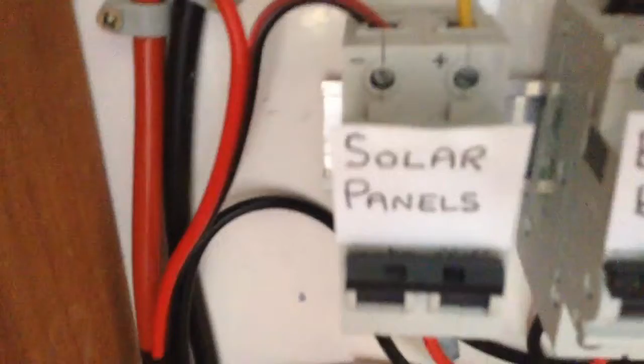From the ammeter we go to a DC circuit breaker. It is an overload protector and a cut-off switch in one. This is a double pole circuit breaker. It's recommended to use double pole isolating breakers - it's a breaker and an isolating switch together, so it disconnects both the positive and the negative of the solar panels. This is a 10 amp breaker.